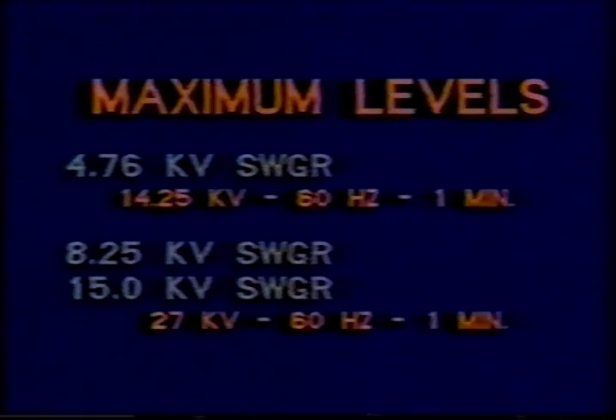This field test should be made before the main cables are connected and should not exceed 14.25 kilovolts, 60 hertz, 1 minute for 4.76 kilovolt switchgear, and 27 kilovolts, 60 hertz, 1 minute for 8.25 kilovolt and 15.0 kilovolt switchgear. Transformer primary fuses should be removed and surge protective devices such as capacitors and arresters disconnected during high potential tests.